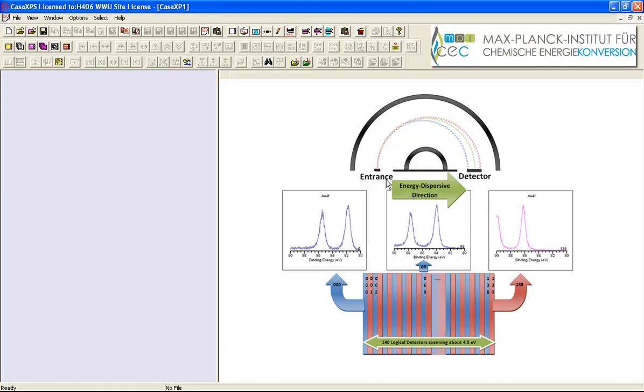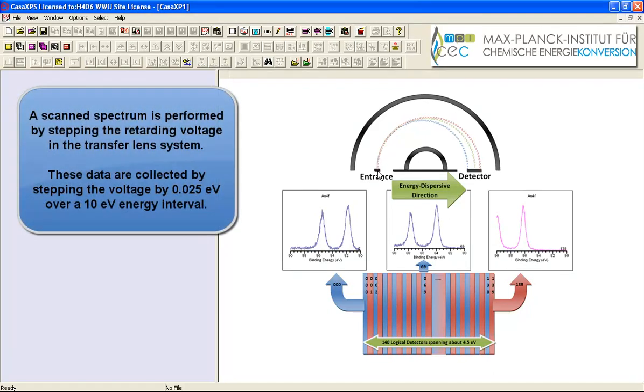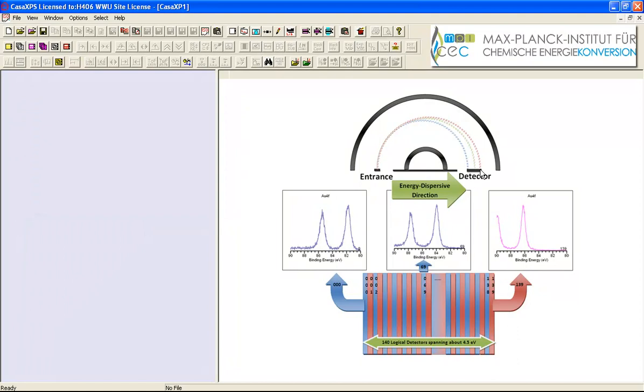And the reason for this is that the pass energy for the hemispherical analyzer is established and then electrons entering the hemispherical analyzer for the given matching pass energy will then be dispersed. And the more energetic electrons hit one end of the detector while the less energetic electrons hit the other end and the ideal energy hits the detector somewhere in the middle.